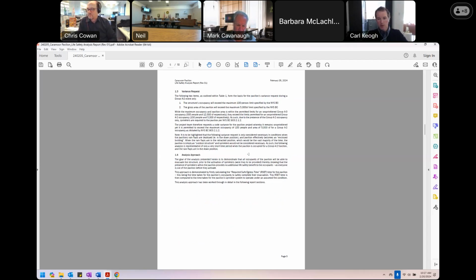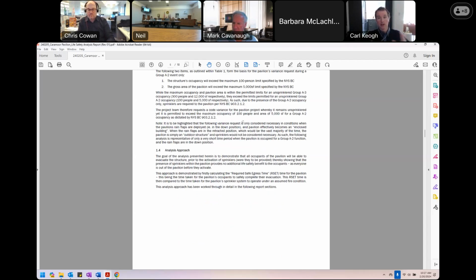Section 1.4 on page 5 outlines the goal of this analysis: to demonstrate that occupants of the pavilion structure would be able to evacuate prior to the activation of any sprinklers, if we had any, thereby showing that the presence of sprinklers within the pavilion provides no additional life safety benefit to the occupants. That's not to say having sprinklers doesn't provide other benefits, not to the occupants, because they're all standing outside, and we can get onto that piece as well.